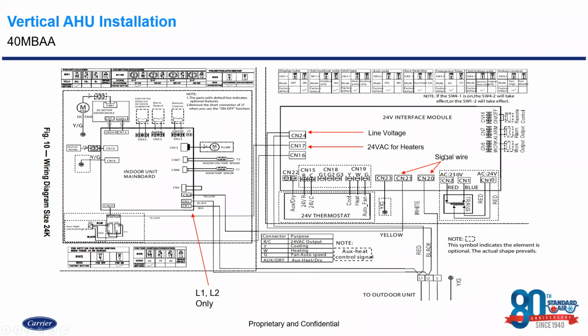Now you can see here I have a few notable things marked on where the signal wire feeds into the interface so that it can communicate properly with the main board, and then also the line voltage that's being sent to the interface, which has its own transformer inside of it that steps down that line voltage to 24 volts AC control voltage for the thermostat. And then that same 24 volts is sent out from the interface over to the main board. And you'll see right here in this little dotted line is where our Molex plug is for our auxiliary heat, which is really nice with the prepackaged kits for the auxiliary heat. Depending on the kilowatt rating, all you're doing is essentially plugging in a Molex plug and then sliding this electric heat kit into a pre-designed slot inside the actual air handler itself. So it's pretty much plug and play for getting the electric heat installed in this cabinet.